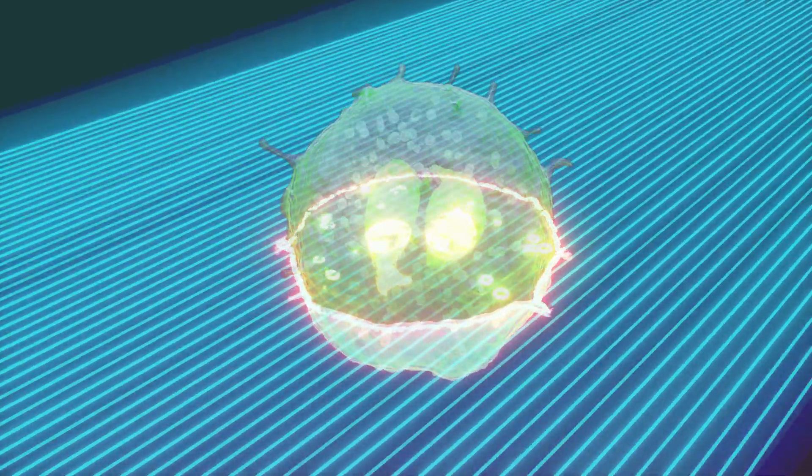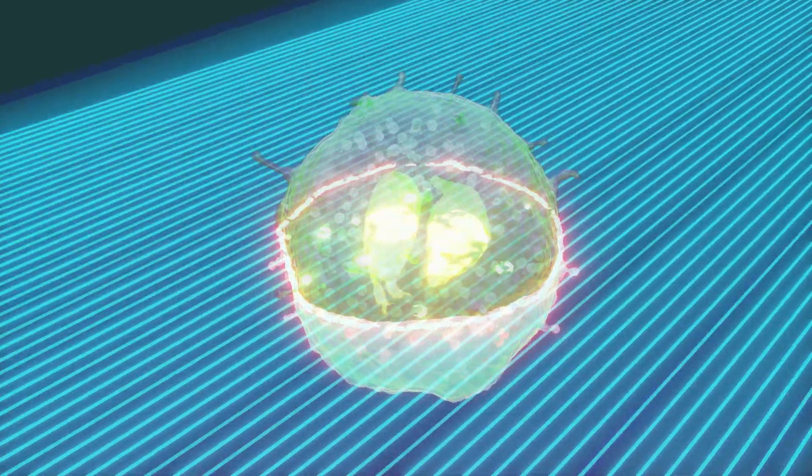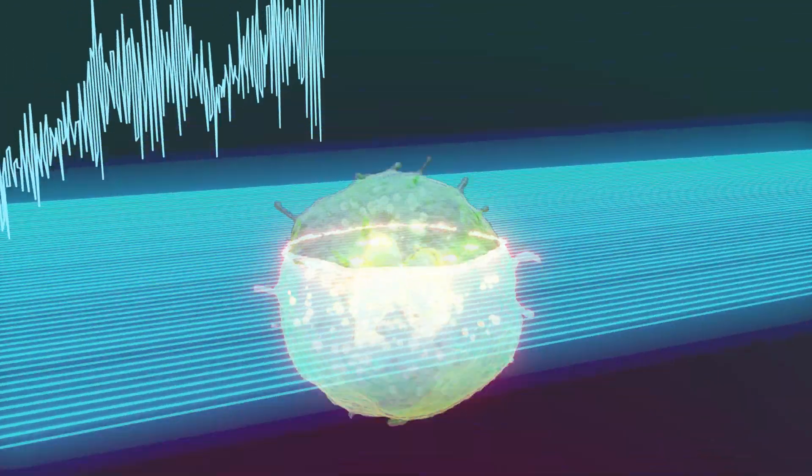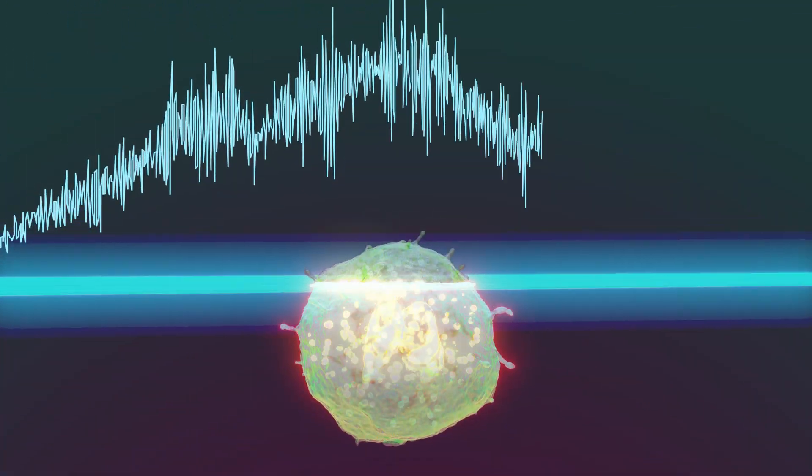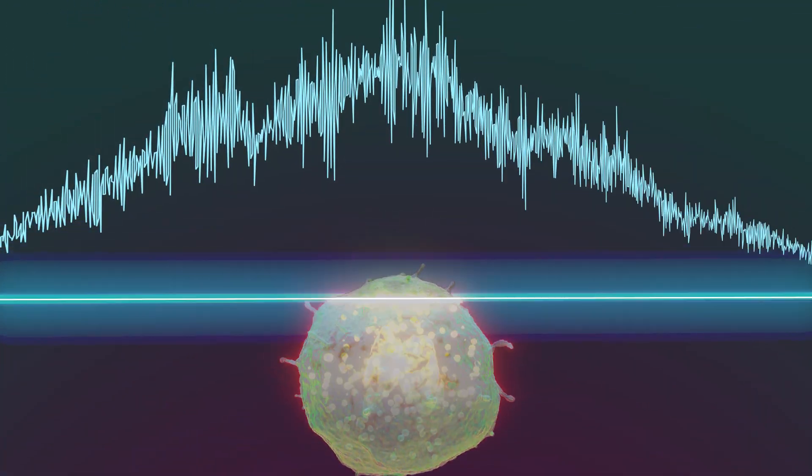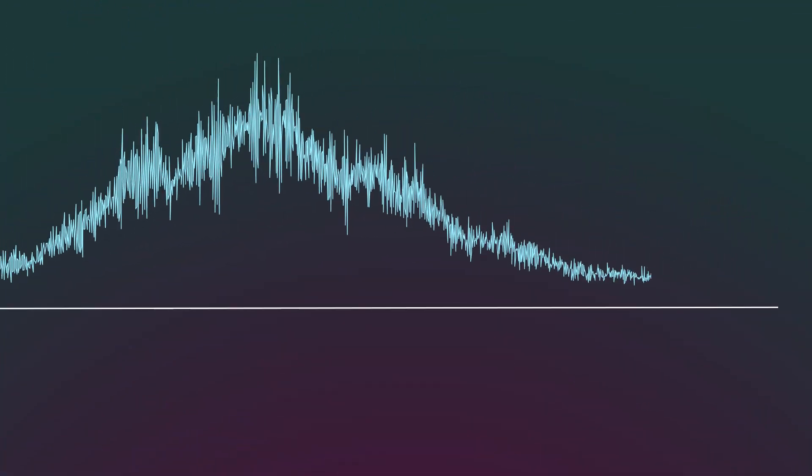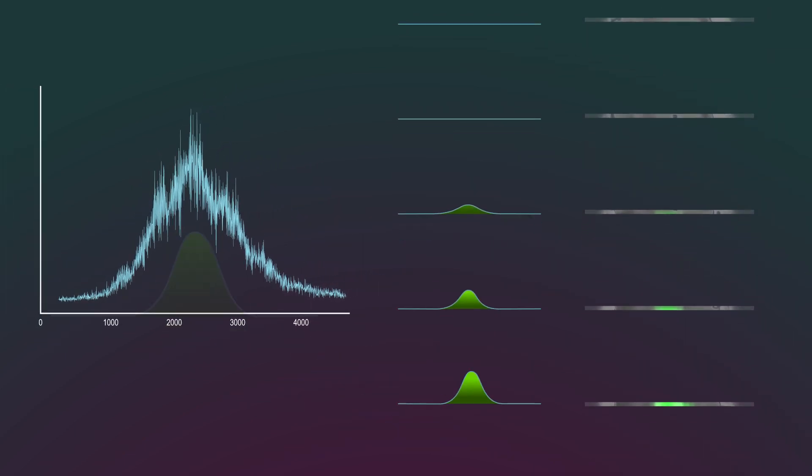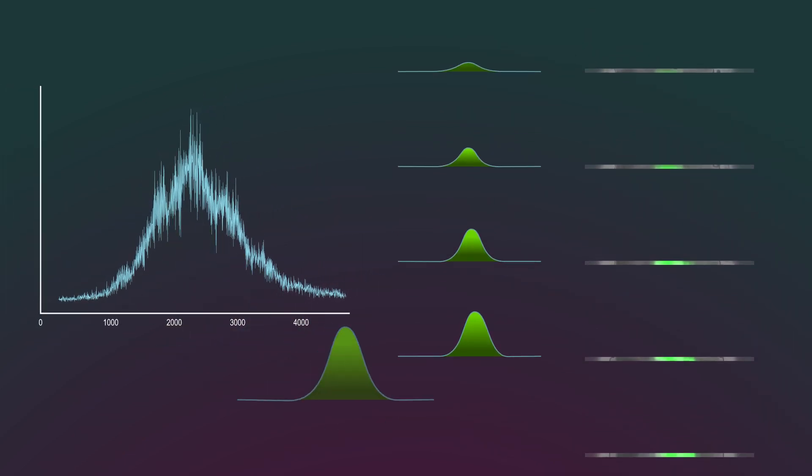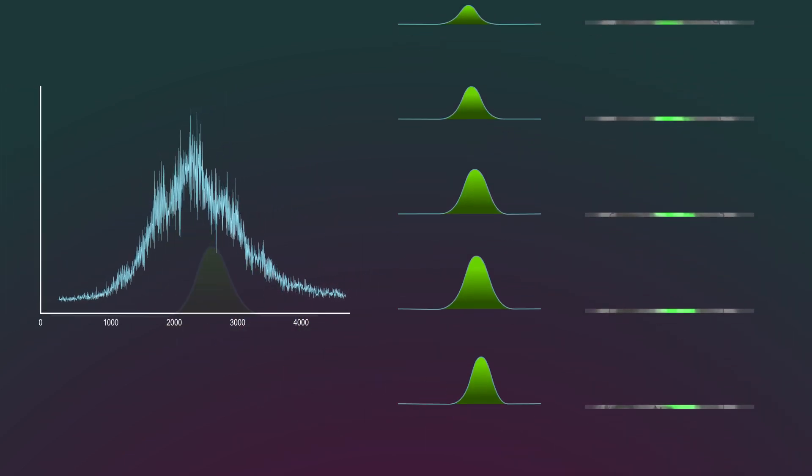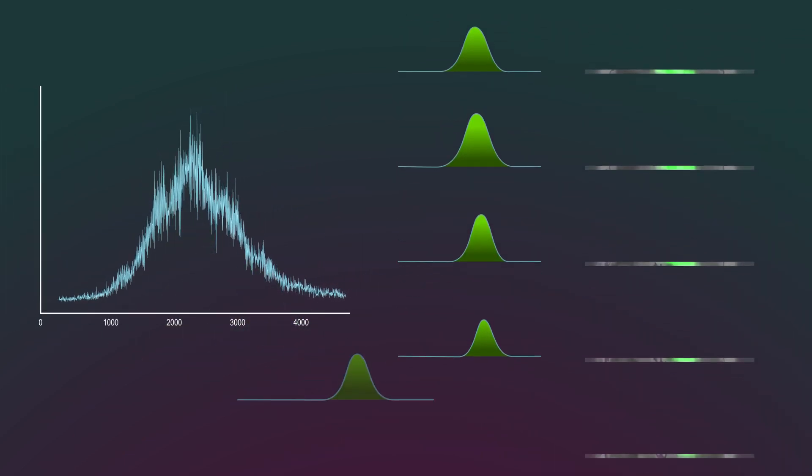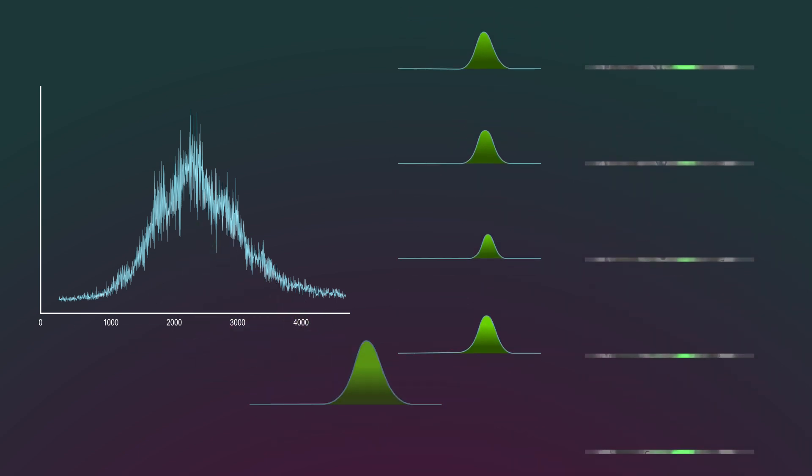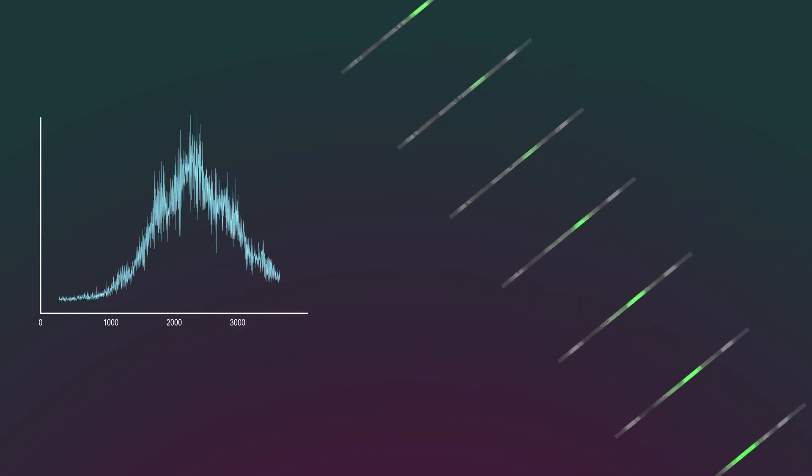As a cell passes through the array of beams, each beam generates a signal that is collected onto a photomultiplier tube. Frequencies are mathematically distinguishable, making it possible to separate each beam from the complex combined signal generated by a passing cell. The frequencies are constructed to produce a complete image.